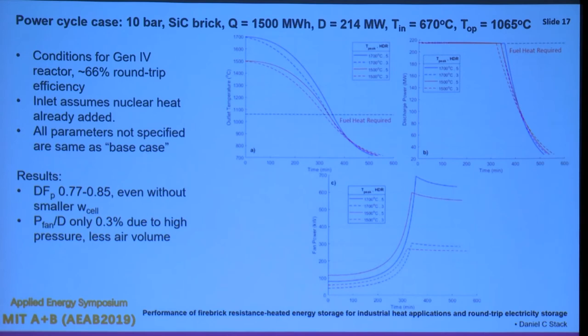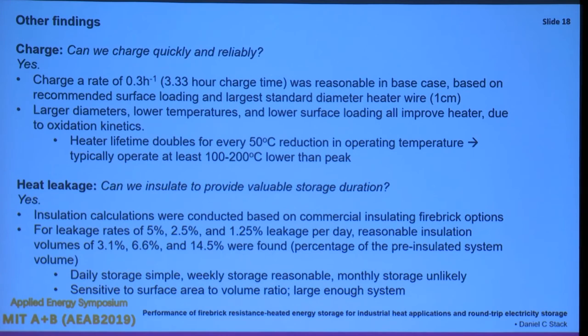For high-pressure systems, we can get similar great performance — almost 0.9 energy out at constant rate with low fan power — characteristic of a system with 66% round-trip efficiency, essentially acting like a battery or pumped hydro station. Other key findings: we can charge quickly in three to four hours or less with enough heaters installed, suitable for daily cycling. Heat leakage is low — standard two to three percent loss per day — so energy can be stored for a week or more.